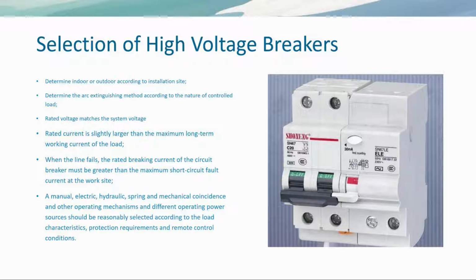At the same time, make sure that the rated voltage of the circuit breaker is consistent with the system voltage. The rated current of the circuit breaker is required to be slightly larger than the maximum long-term operating current of the load. The circuit breaker should have sufficient breaking capacity. When the line fails, the rated breaking current of the circuit breaker must be greater than the maximum short-circuit fault current at the worksite. If the requirements cannot be met, a reactor should be used to limit the short-circuit current, or use a circuit breaker with a larger capacity.